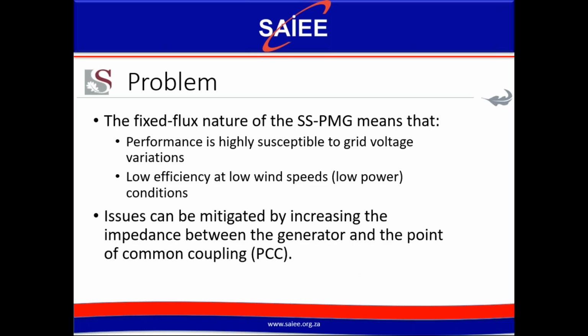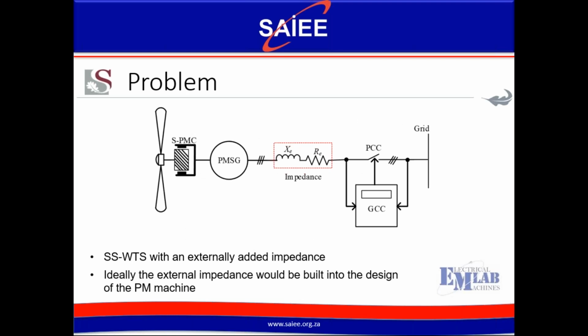However, the fixed flux nature of the permanent magnet synchronous generator means that its performance is highly susceptible to grid voltage variations, and its efficiency is particularly low at low wind speeds. This issue can be mitigated to some extent by increasing the impedance between the generator and the point of common coupling, or PCC, as is shown in this slide. However, ideally, this external impedance would be built into the design of the generator rather than being an externally added component.